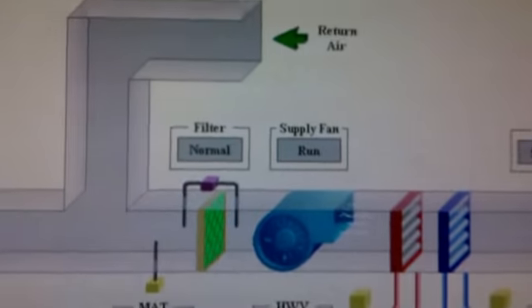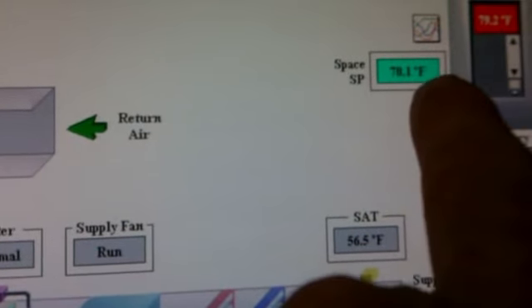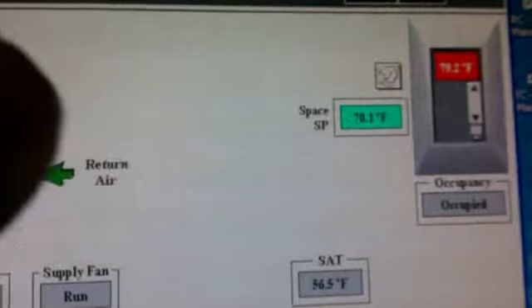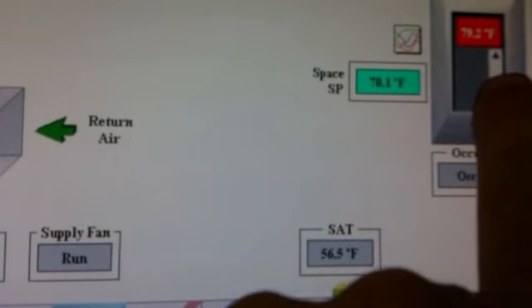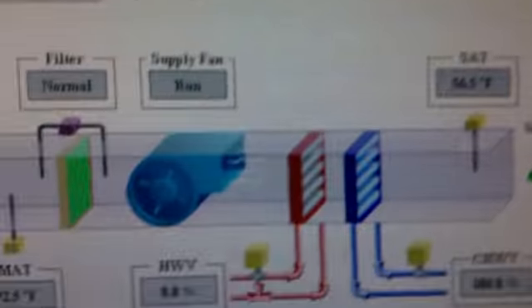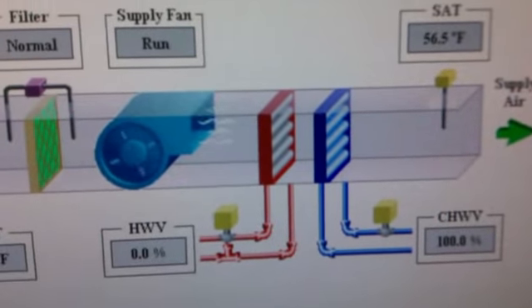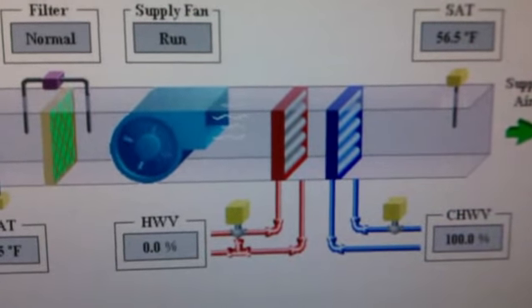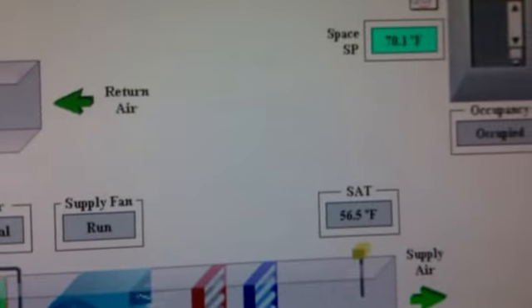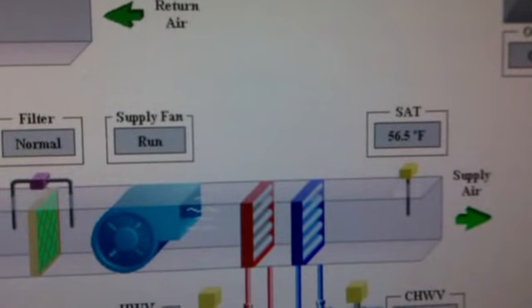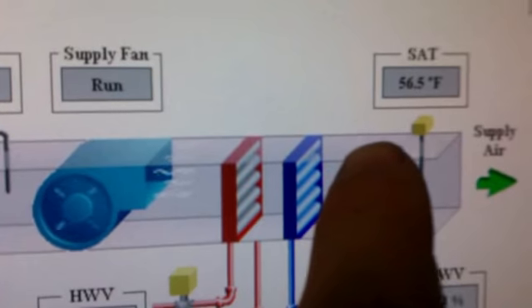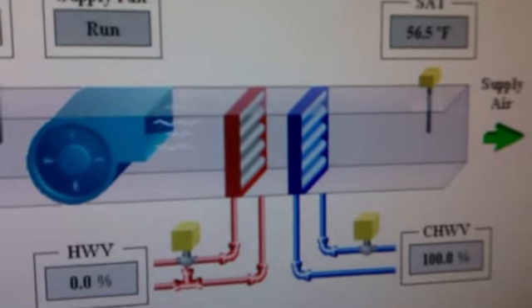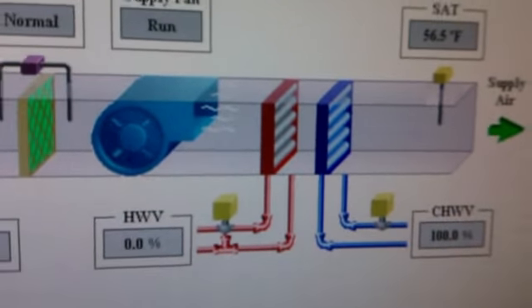Since this is a kitchen and it's set for 78 degrees, 78.1, don't know why it's set for that. And it's 79.2, obviously it's just 100% cooling and it doesn't keep up, which is normal for a kitchen. But a kitchen that's staying under 80 degrees most of the time, that's pretty good. And because the supply temperature is 56 degrees, so it's cranking out the temperature.